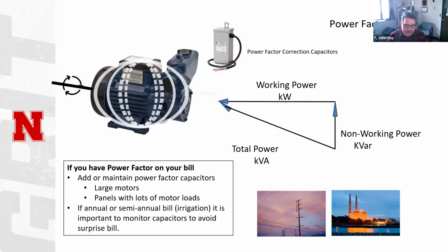So if you have power factor on your bill, here's a couple of things I wanted to note. You want to add or maintain power factor correction capacitors on your large motors or on your panels that have lots of large motors on them. There's different types of capacitor banks. You can put big ones by the panel, or you can put littler ones on each motor. Different pros and cons to each of those. You want to add those. Some utilities on irrigation systems have required these for years, but not charged for power factor. Now we're adopting the power factor charges. So some people in Nebraska are going to discover they already have the power factor correction device there. All we have to do is make sure it's working. So then it is just maintain that system.